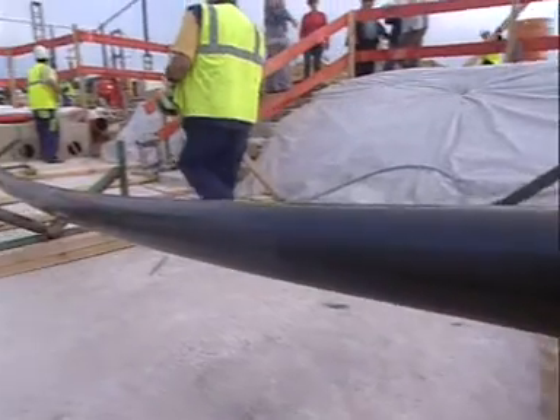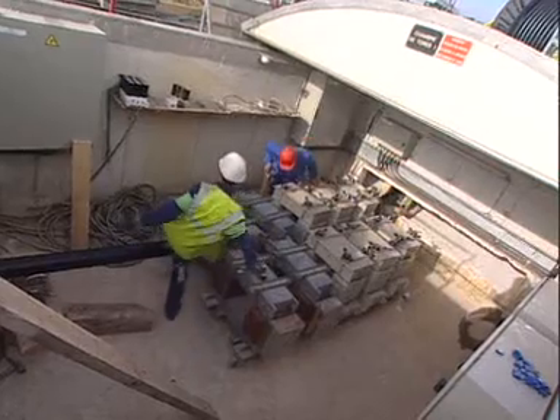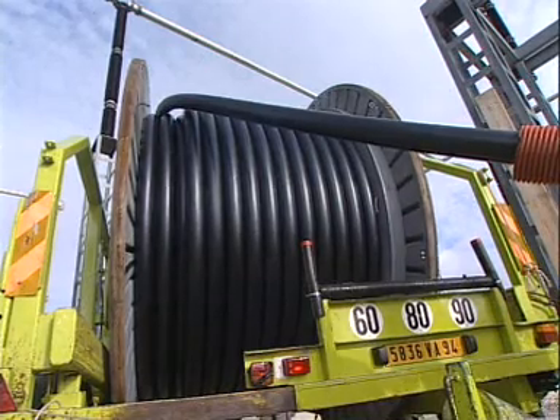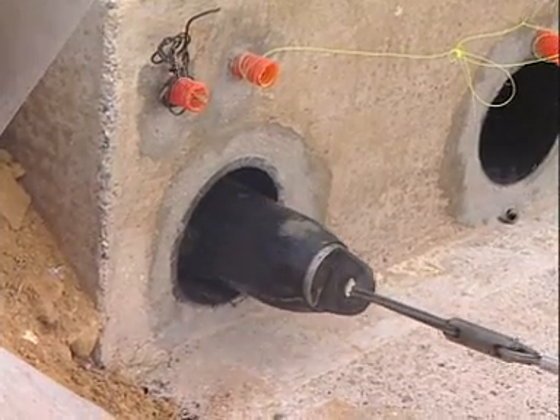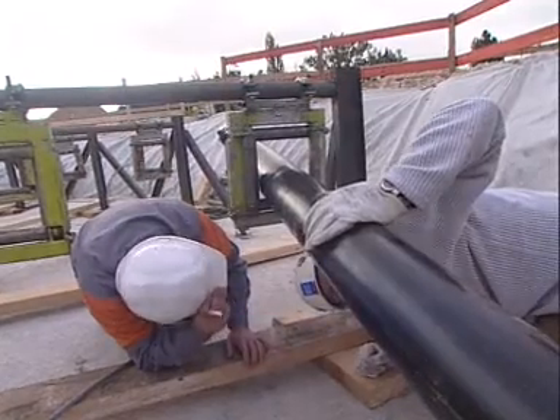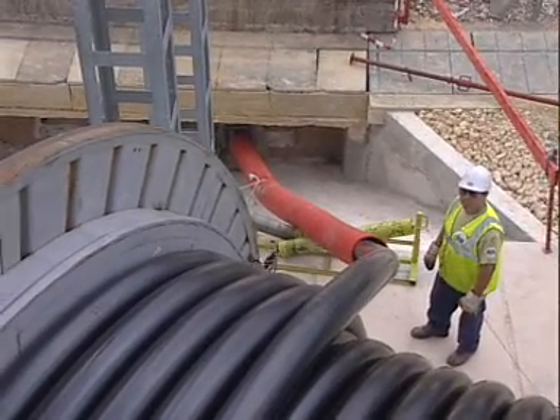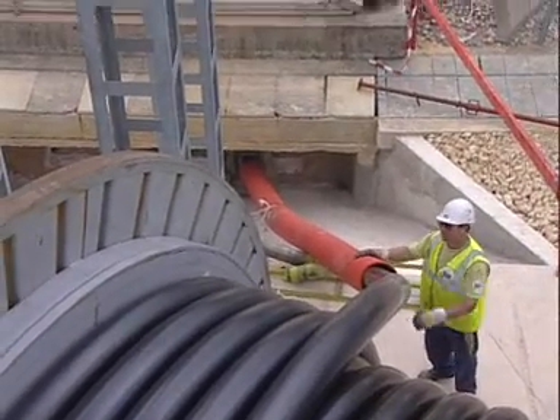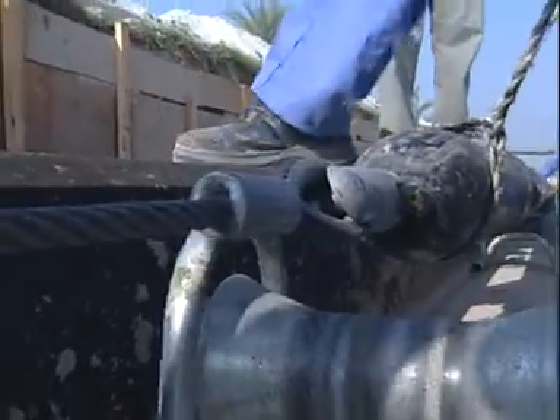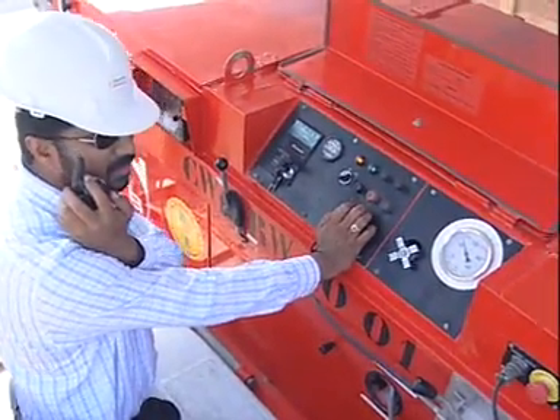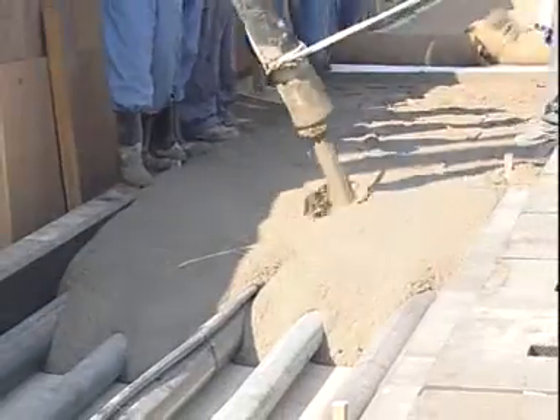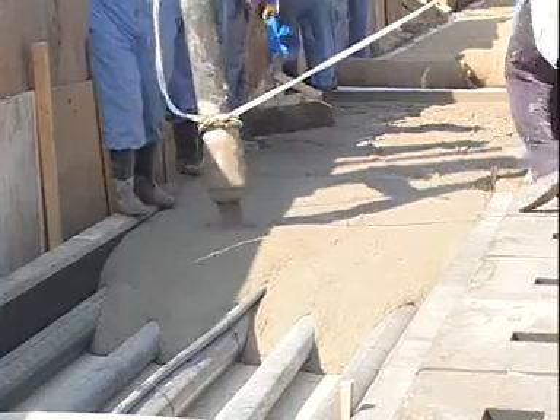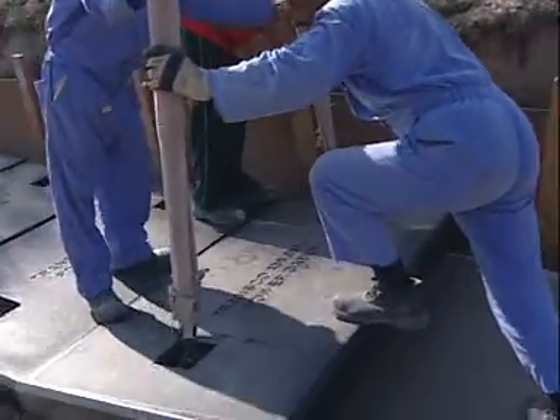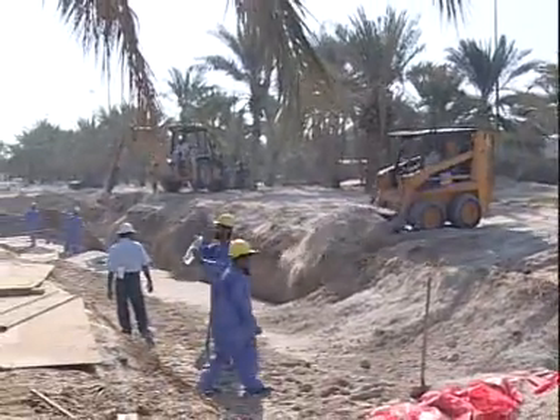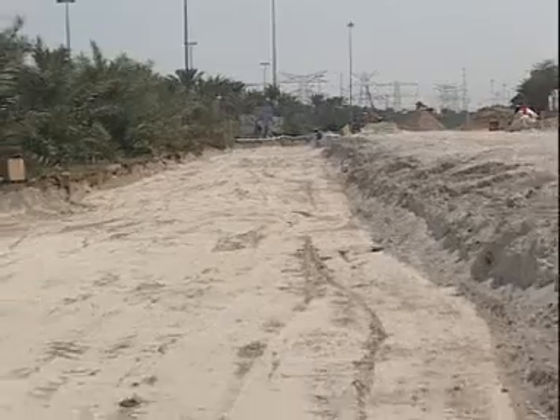This loop contains several sections representative of the different laying methods used in the Abu Dhabi installation. Laying in ducts, laying in trenches with controlled backfill, laying in ground level conduit. After the trenches have been dug and the prefabricated conduit installed, the cable is unreeled and laid. The conduits are then filled with thermal backfill, which is a mixture of sand and cement, before the covers are put on. A layer of what is called crusher run is then added before a safety grating is placed on top. The trench is then filled with high-quality sand to allow the overlying ground to be restored to its initial condition.